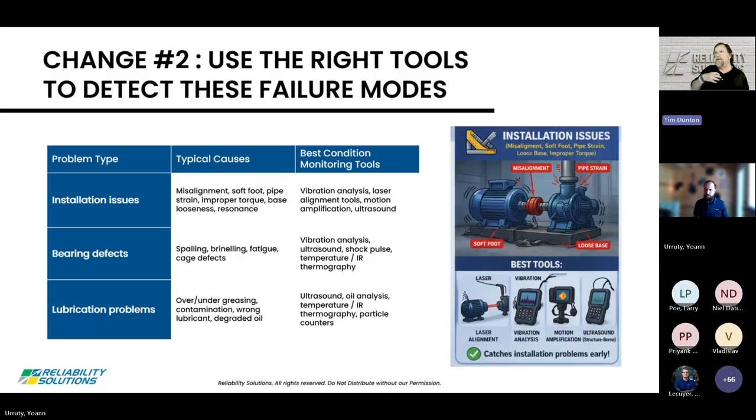Certainly, we try to encourage PdM and condition monitoring folks to come at it from several different angles. Don't put all your eggs in the vibe basket. If you think you've got something going on in vibe, go ahead, hit it with infrared. See if that confirms your hypothesis. And of course, if you've got a misaligned machine, chances are the coupling will be running harder than normal.